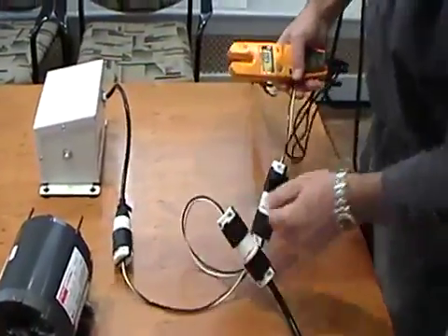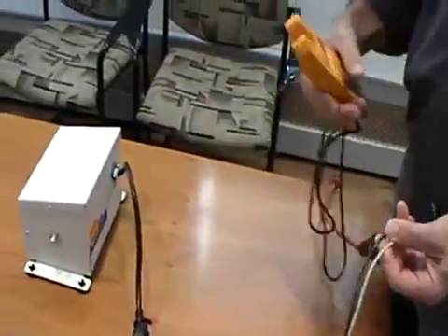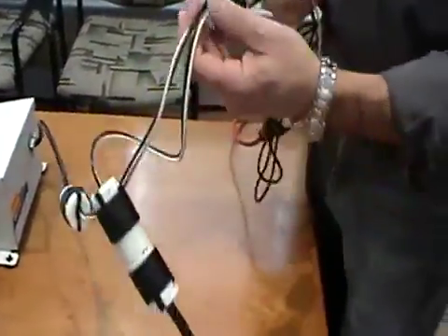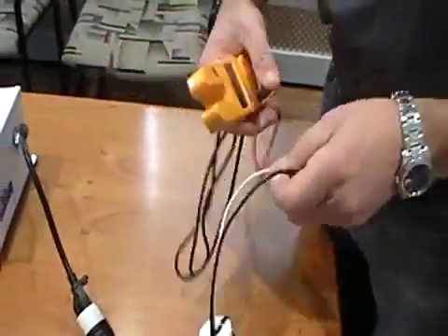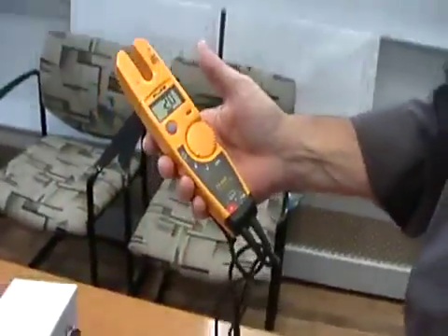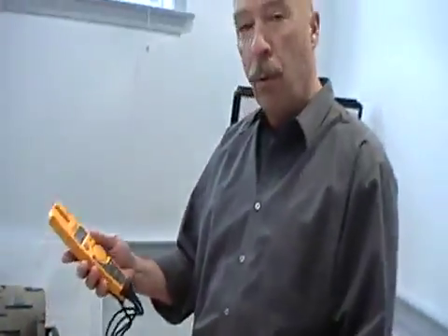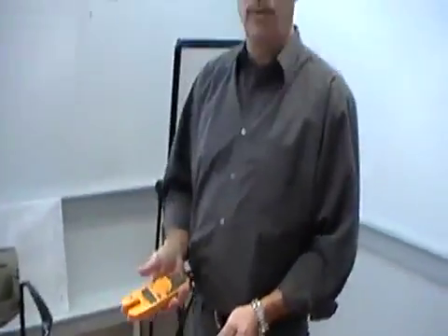Now we're going to check the power on the distribution system. In theory, we should have eliminated all that wasted current off the distribution system from this point back. 2 amps. We've taken 60% of the wasted current off of the distribution system, trapped it at the motor load. So what this does is greatly reduce the strain on the distribution system.